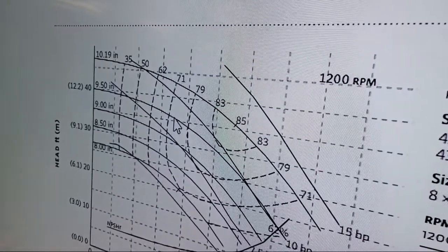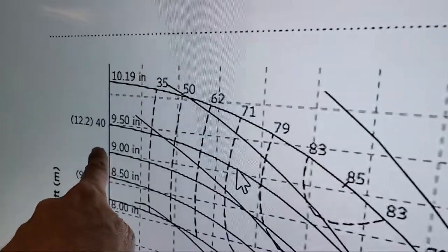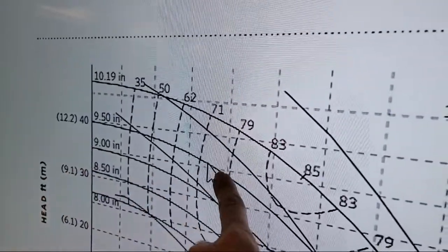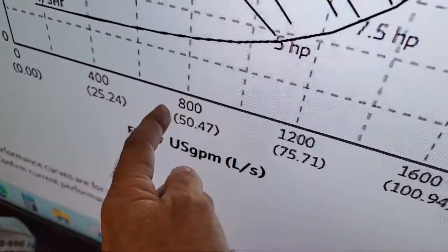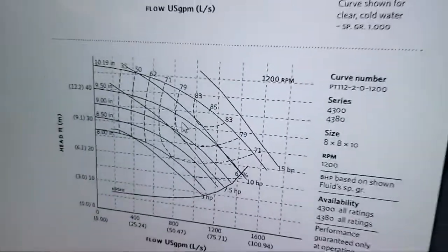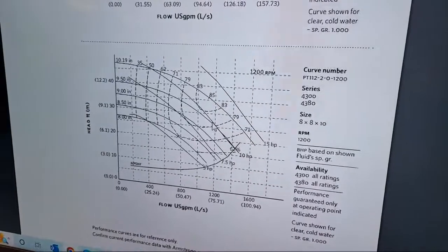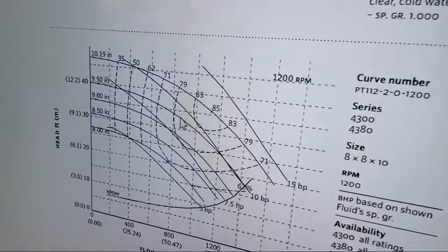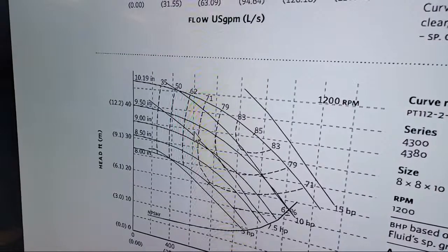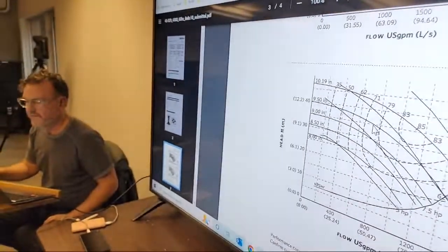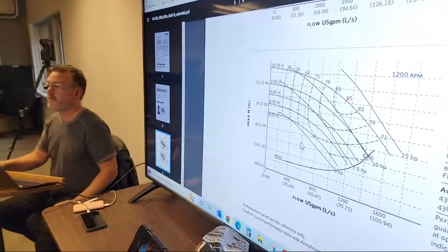35, whatever the installation, because the energy that we use in buildings is based on it. You're saying 35 feet of head, right? Yeah, 35 feet, so I'm going to be just under 800 gallons per minute. In a constant speed pump, if I throttle a valve or something changes, it's going to slide up the curve this way. Now my head, my energy, is going up, and my flow is going down. Well, that can be a problem, right?